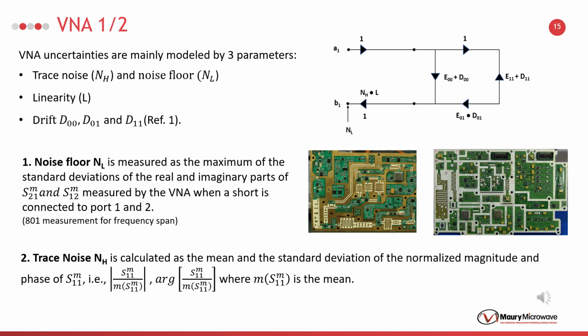Noise floor is the power level of the noise signal generated by the electrical components of the VNA. To calculate the noise floor and linearity, first, maximum values of the real and imaginary parts of S12 and S21 values are considered. To measure S parameters, first, IF bandwidth of the VNA is set. The VNA ports are terminated with a reflect, such as a short, then a few hundred measurements are captured. For trace noise, mean and standard deviation of the normalized magnitude and phase values of S11 and S22 are considered. These values can be taken as the standard uncertainties of magnitude and phase of trace noise.